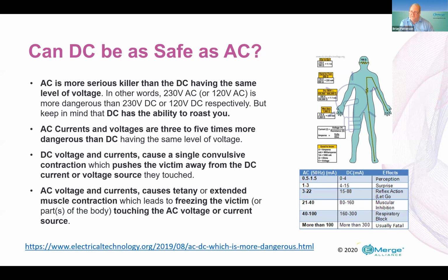But that also means peak voltages on the AC side are higher than the actual label voltage, right? That's correct, and there have already been studies comparing high voltage DC to AC as far as safety goes, not to mention doing things differently like grounding and solid state protection devices. DC is inherently safer because AC is a fibrillation source and actually stops your heart, where DC doesn't do that. In fact, the defibrillators they carry around use DC charges to try to get your heart started again. So there have been studies showing DC is safer, and these use cases and voltages compared to where they are in the system are being studied more to prove there are ways to make DC infrastructure ultimately safer than AC power.